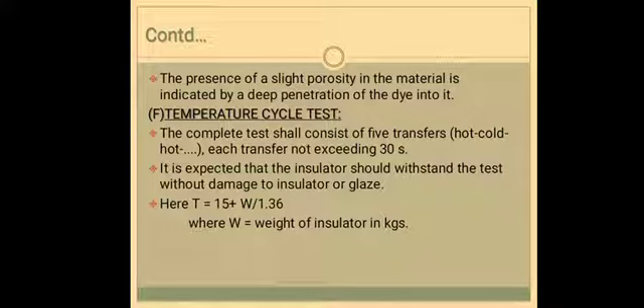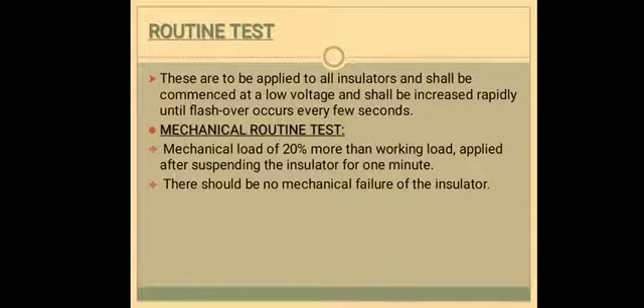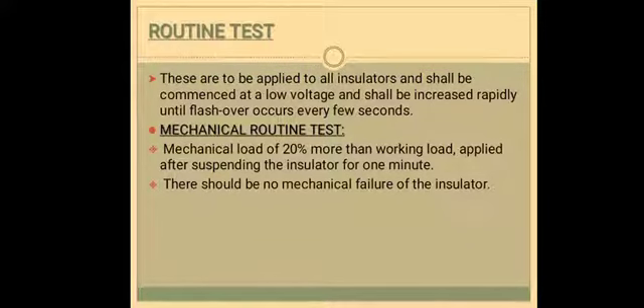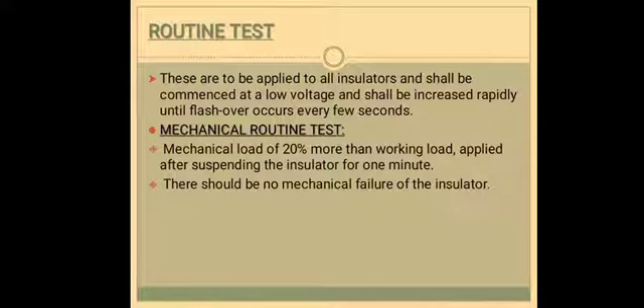The last type is the routine test. Routine tests are applied to all insulators and will be commenced at a low voltage, increased rapidly until flashover occurs every few seconds. The only category in the routine test is the mechanical routine test. In this, the string insulator will be suspended vertically or horizontally, and a tensile load 20% in excess of the maximum specified working load will be applied for 1 minute. As usual, there should be no damage to the string.